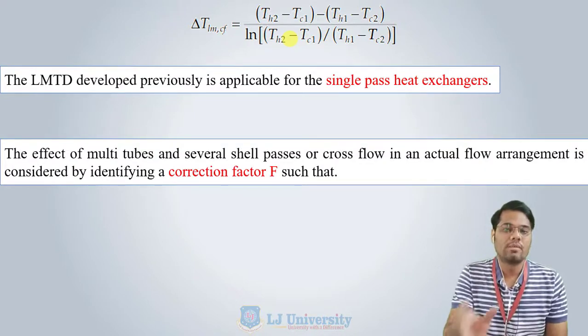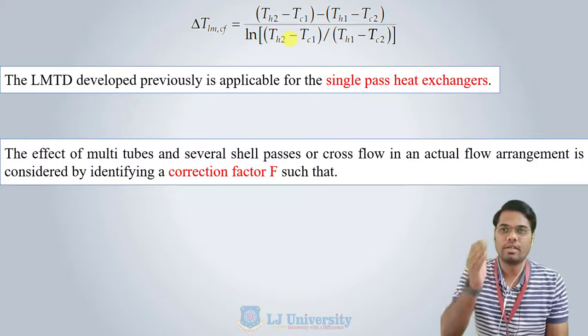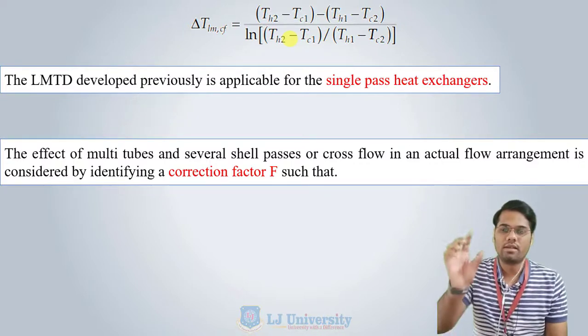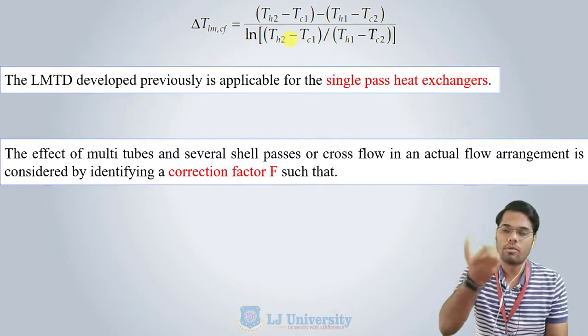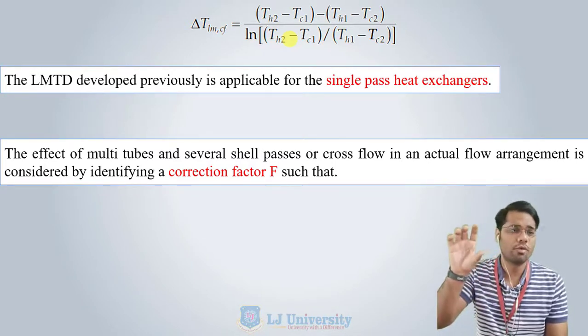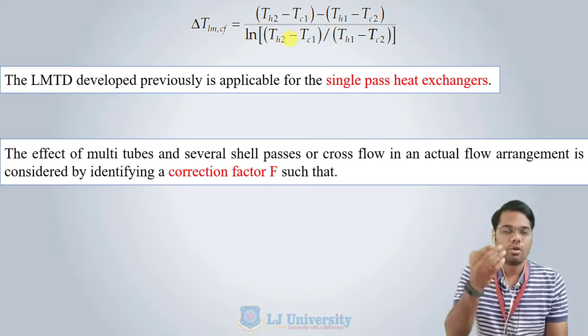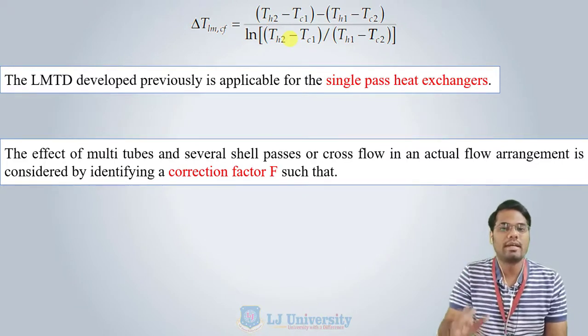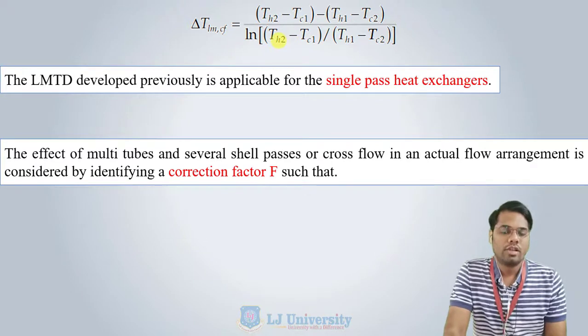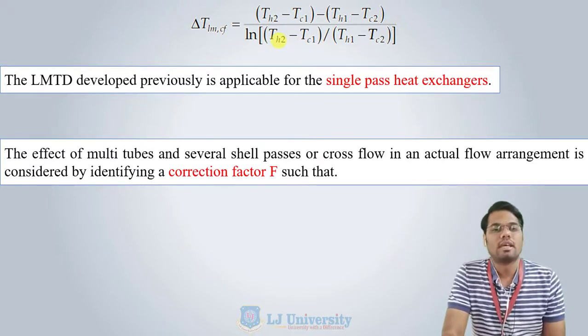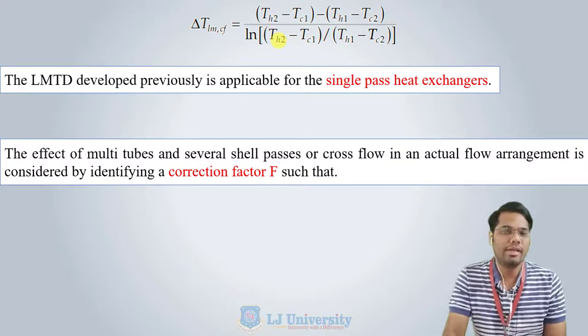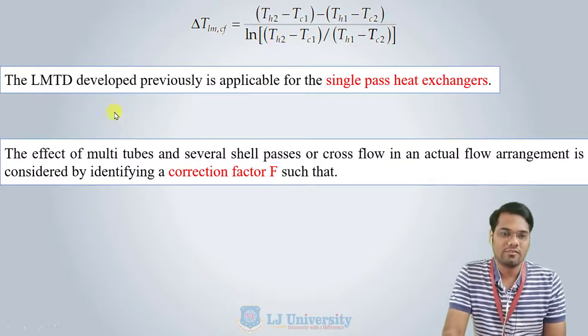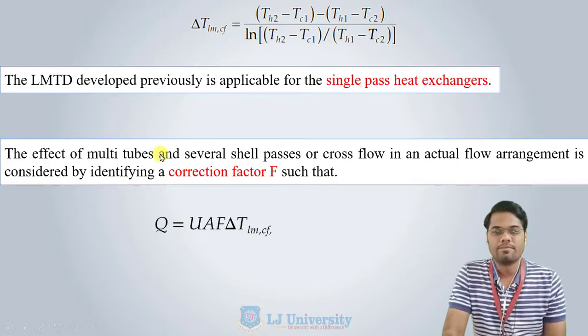This is because of effects due to multiple tubes and several passes. In a cross flow heat exchanger, for a particular region two fluids may flow in the same direction, while for another region they flow in opposite directions. So for one pass it will be a parallel flow configuration and for another pass it will act as a counter flow heat exchanger. Therefore, for multipass and cross flow arrangements we need to add a correction factor, which can be found using certain non-dimensional terms.